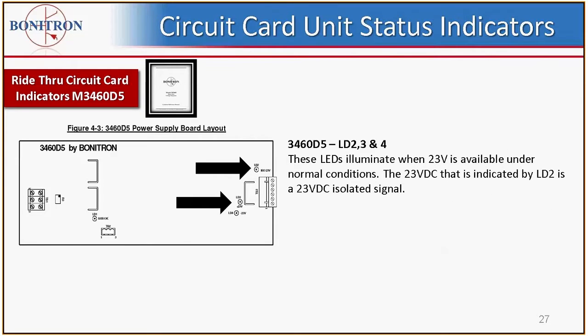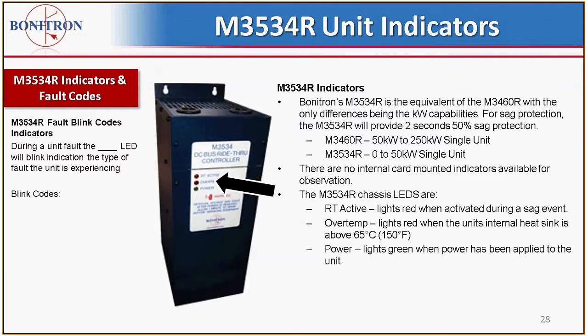Also on the D5 power supply board are 23 volt plus and negative voltage indicators, and they will illuminate when 23 volts is available under normal conditions. And there's also a 23 volt DC that is indicated by LD2 as a 23 volt DC isolated signal. This signal is used internally to the ride-through event to provide 23 volt DC power. And those are the main 3 circuit card indications.